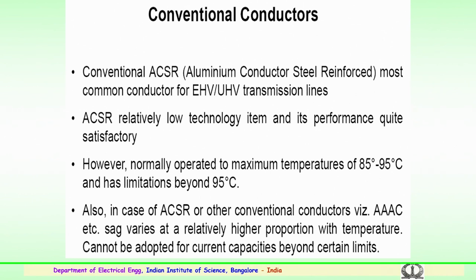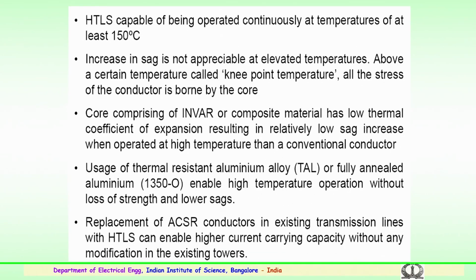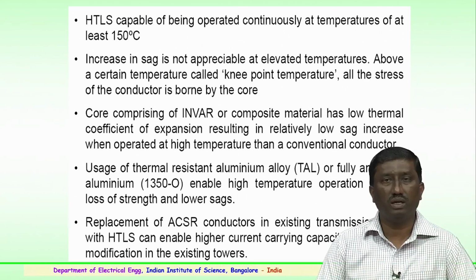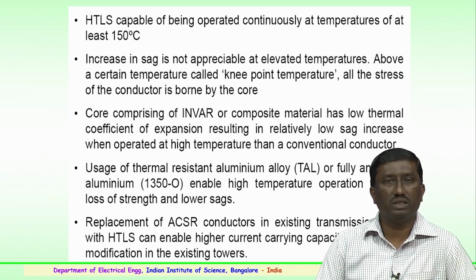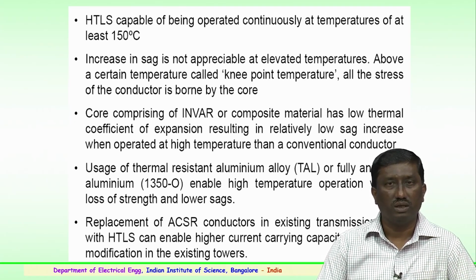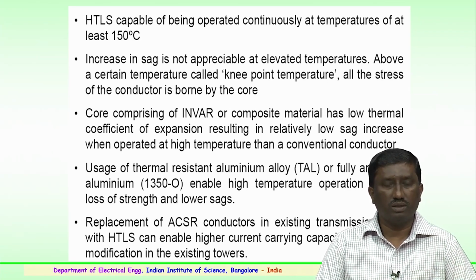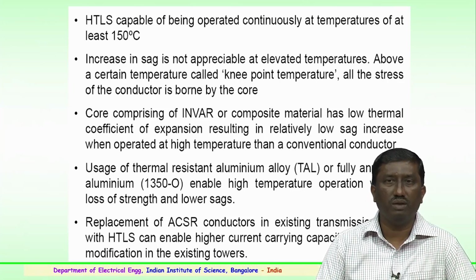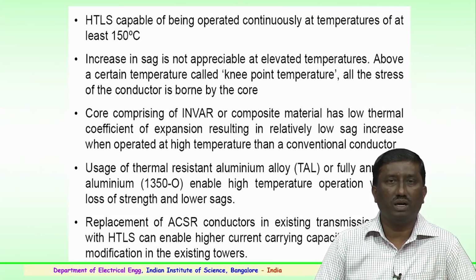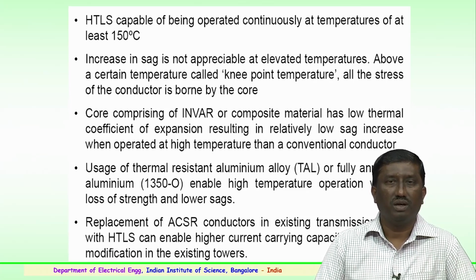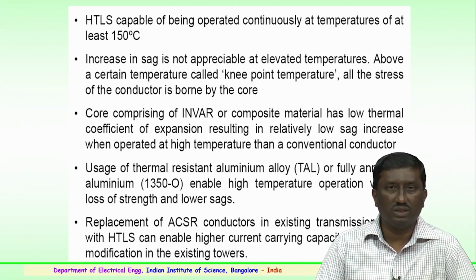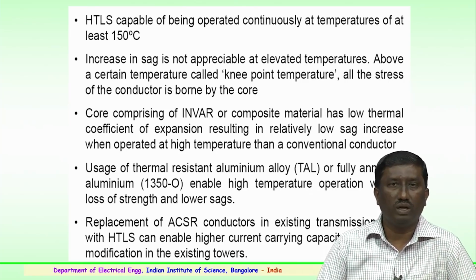So, an alternative and newer technology is being recommended, and it is being used and operated in the country at very high temperatures. The HTLS, or high temperature low sag conductors which we have discussed, are capable of being operated continuously at a temperature of at least 150 degrees, a minimum of 150. We have seen their performance in the laboratory up to 200 degrees.